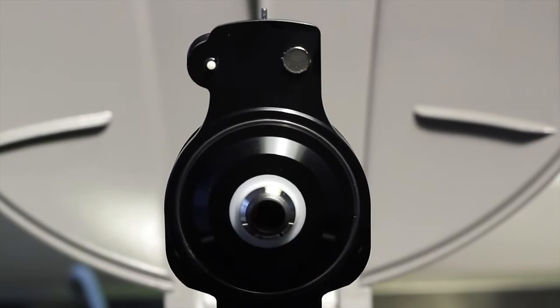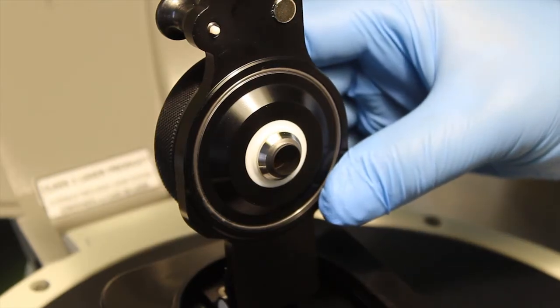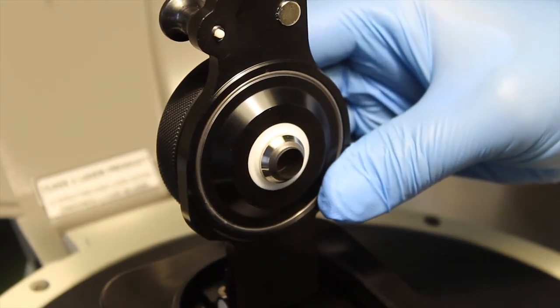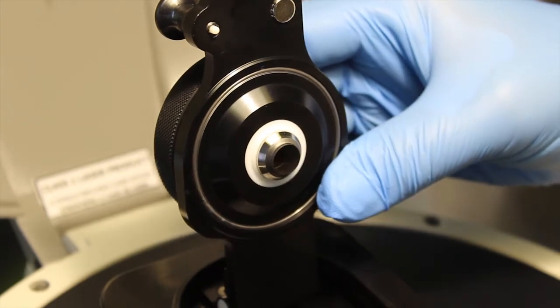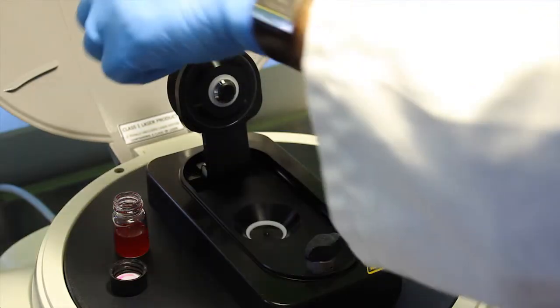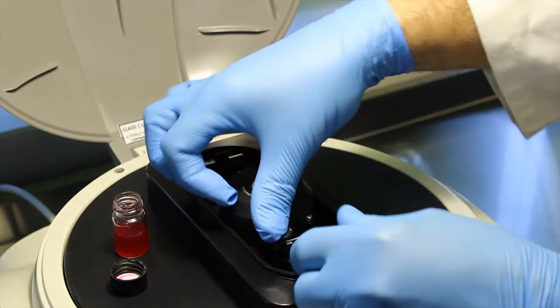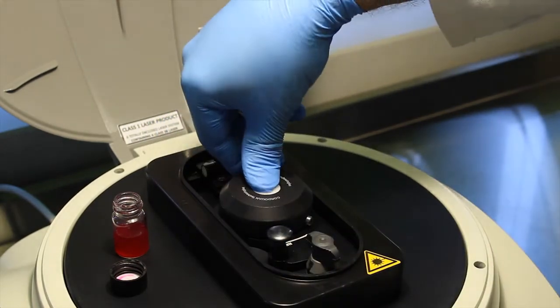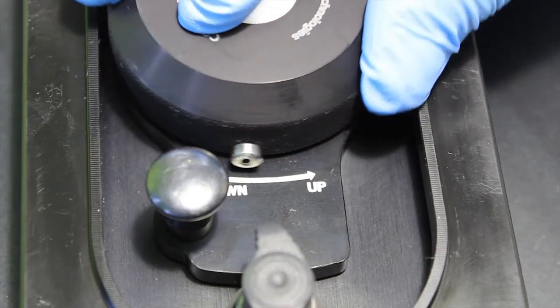Indeed, thanks to its unique and original concept of liquid-thin film measurements with two preset thicknesses, VASCO allows to adapt the measurement configuration to the sample and to prevent spurious signal and measurement artifacts such as multiple scattering and local heating. The benefits of this thin film concept are numerous.